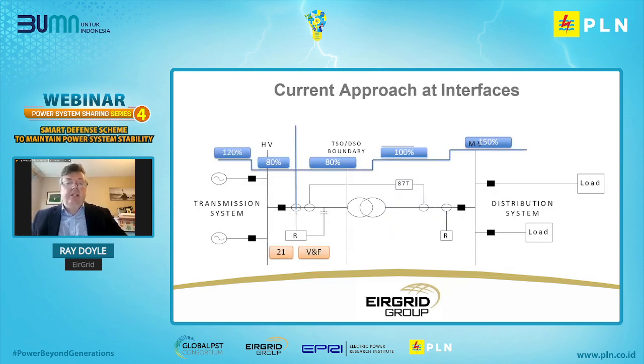So we've started fitting, as you can see there, current transformers and voltage transformers, distance protection, and voltage and frequency protection. You can see the distance relays are typically set with the first step forward at 80% into the transformer, the second step looking 100% into the MV busbar, and the third forward step looking maybe 150% down into the distribution network. Then looking the other direction, back towards the HV busbar, the first step is set at maybe 80% of the shortest feeder connected to the transmission station. Next slide, please.